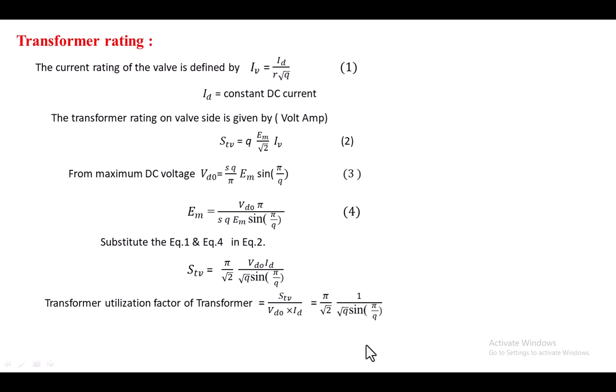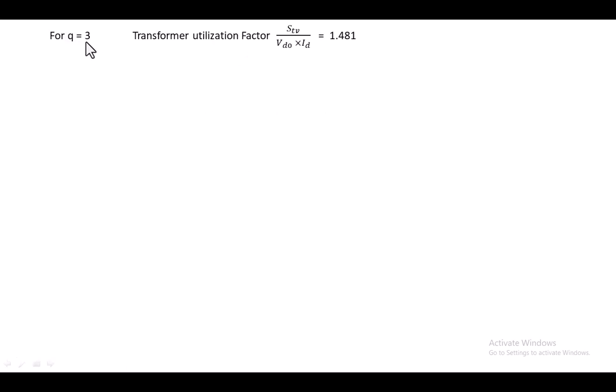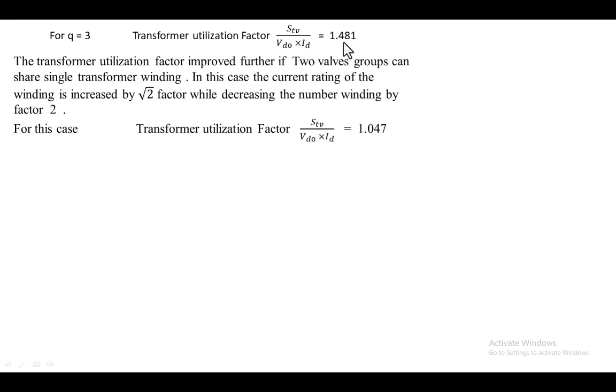The transformer utilization factor depends strongly on the q value. For q = 3, meaning three devices per commutation group, the transformer utilization factor is high at 1.481. This also matches the number of phases used to supply power to the converter. The transformer utilization factor can be further improved by using one transformer winding to supply power to two valve groups simultaneously, which increases the current rating of the winding by a factor of √2 and reduces the number of windings by 2. In that case, the transformer utilization factor becomes 1.047.